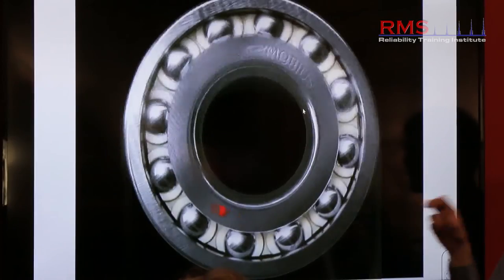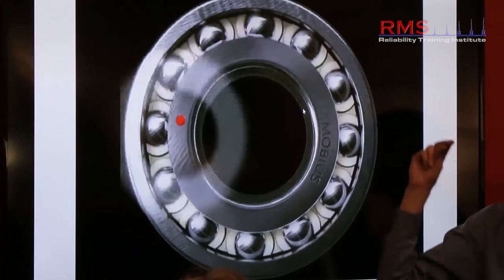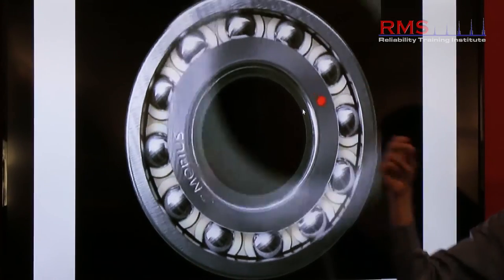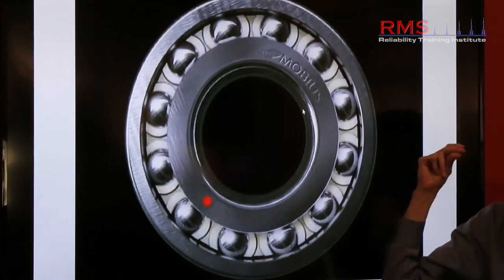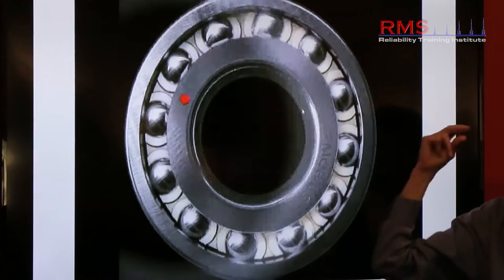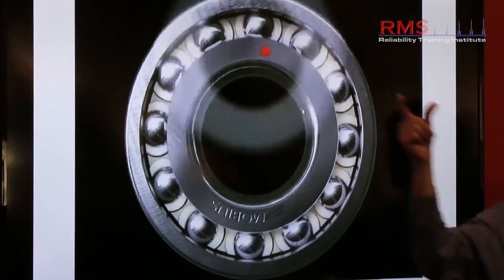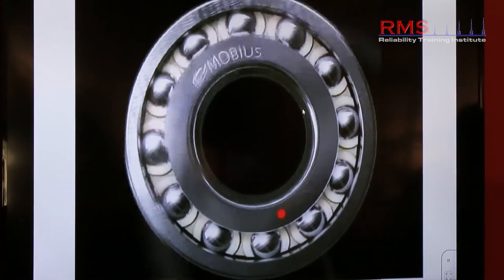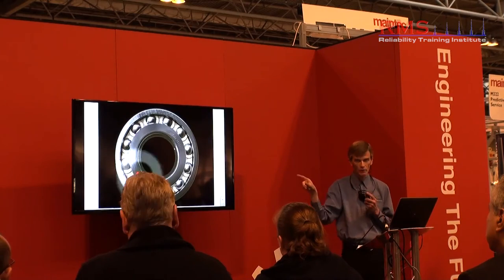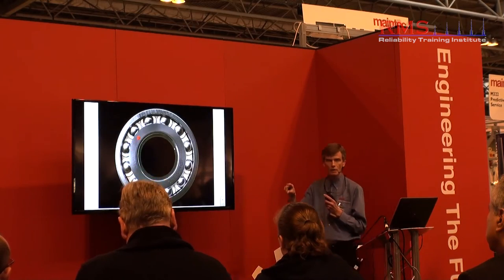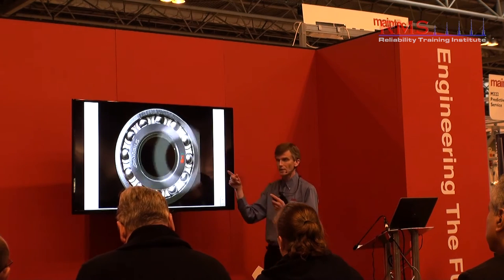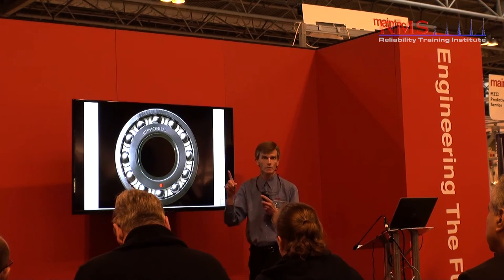The defect here is where that red dot is at 12 o'clock. One shock, two, three, four, five, six, seven, eight — and a bit. Eight and a bit shocks per rotation. Not seven, not eight, but eight point something.